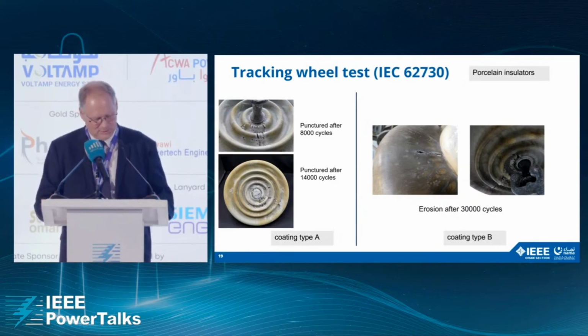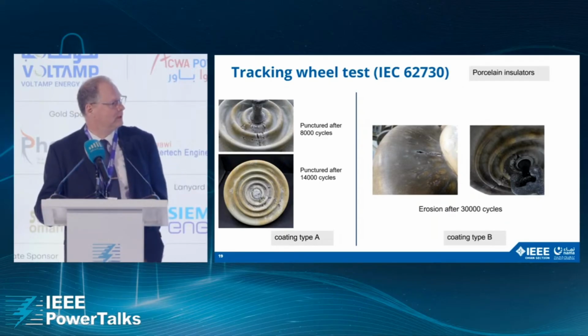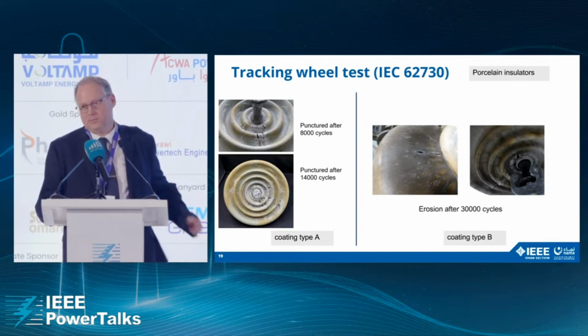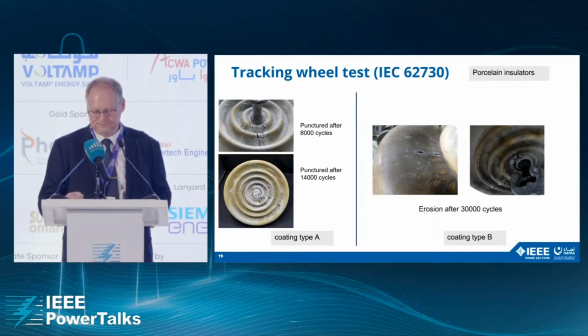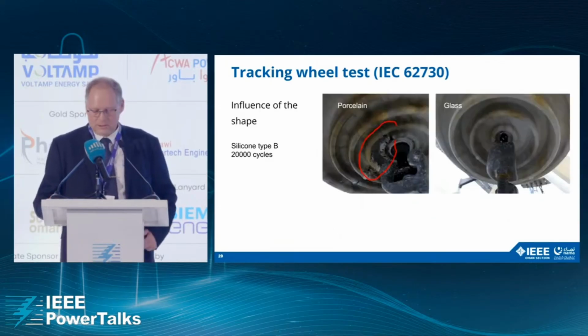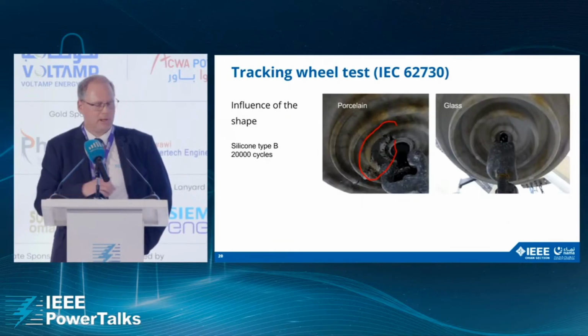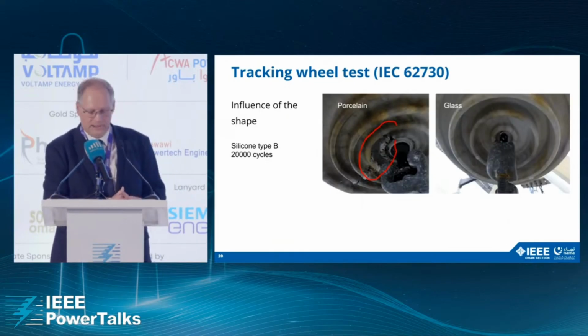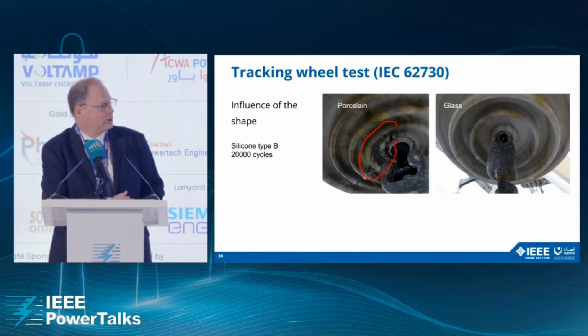The same difference in the behavior of the coating is also observed on the porcelain insulators. Type A, puncture of the porcelain after 8 to 14,000 cycles, whereas after 30,000 cycles, coating type B is still in good condition. So it seems also that while all samples were coated with similar care of adhesion, porcelain is more inclined to lose adherence than glass. And this is most probably due to the shape and the design of the insulator underneath.